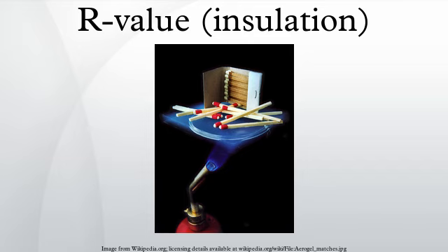Example values: note that these examples use the non-SI definition and are given for a 1-inch thick sample. Vacuum-insulated panels have the highest R value. Aerogel has the next highest R value, followed by isocyanurate and phenolic foam insulations with R-values of 8.3 and 7 per inch, respectively. They are followed closely by polyurethane and polystyrene insulation at roughly R-6 and R-5 per inch.